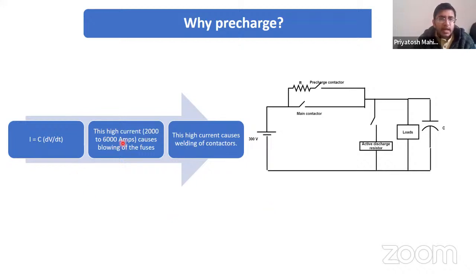So you can see how much high current can initially flow - 2000 to 6000 amperes. Normally we see this type of current in transmission systems or in fault situations, but not in a 400 volt situation. So now you understand that this much current cannot be handled by the batteries - immediately the battery will blow.